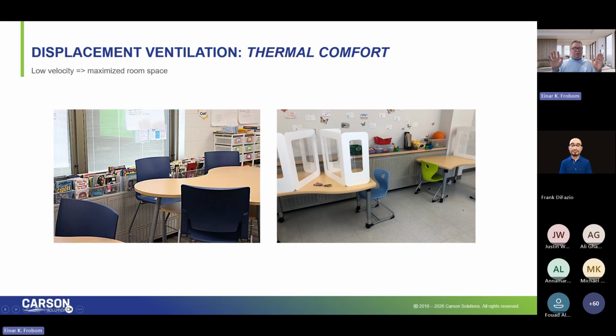I don't have air coming out the top unless I apply the rear fin tube mechanism. So Jenny sitting here with her exposed Birkenstocks, if she felt a draft, you can put your hand right up to our diffuser, right on the diffuser outlet, and you will not feel a draft. That velocity is so slow that Jenny can sit here. If she felt a draft, she'd complain. They wouldn't leave these rooms in this arrangement. Same thing with Billy and Bobby sitting here. If they felt cooler or warmer than Becky or Sue on the other side of the room, someone would complain. They wouldn't leave these rooms like this.